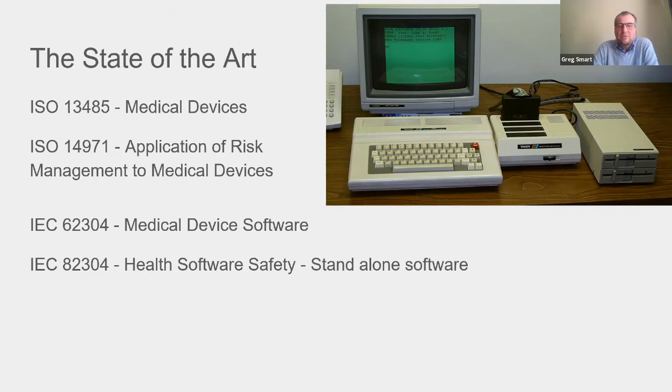The first one, 13485, applies to all medical devices and is not specific to software. 14971 again applies to all medical devices, but specifically looks at how you manage risk. And really, risk is the central underpinning of the standards. And then 62304 and 82304 are very similar, but they consider the 2 different cases.